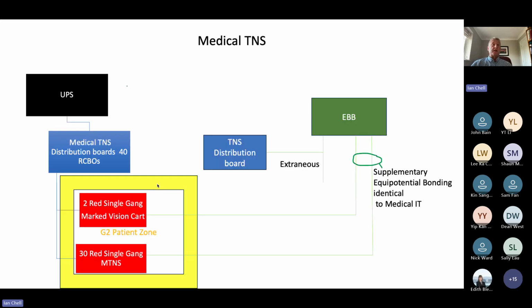So this is the suggestion for medical TNS. You have your UPS and then a much bigger medical TNS distribution board, which probably can take up to about 40 RCBOs. So that means you have a possibility of 40 single gang sockets, each protected by an RCBO. But if you've got medical surgical robot equipment in the location, you can fit 2 time delay RCBOs and supply separate sockets. But if you notice, any medical TNS only goes in the patient zone.